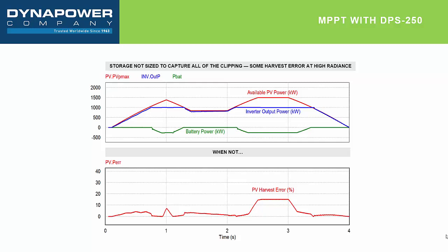And this became a very important design criteria as we set out to develop a DC-DC converter for these configurations. And we've developed an algorithm that essentially does allow the charging and discharging of the storage off that DC PV bus without impacting the max power point tracking. And that's important for perhaps the very obvious reason that as soon as you impact your max power point tracking algorithm, you are impacting the overall efficiency of the system and impacting revenues. So that's a very important design criteria. And it's a question that comes up quite frequently. So we want to point out that this configuration will not impact your max power point tracking.